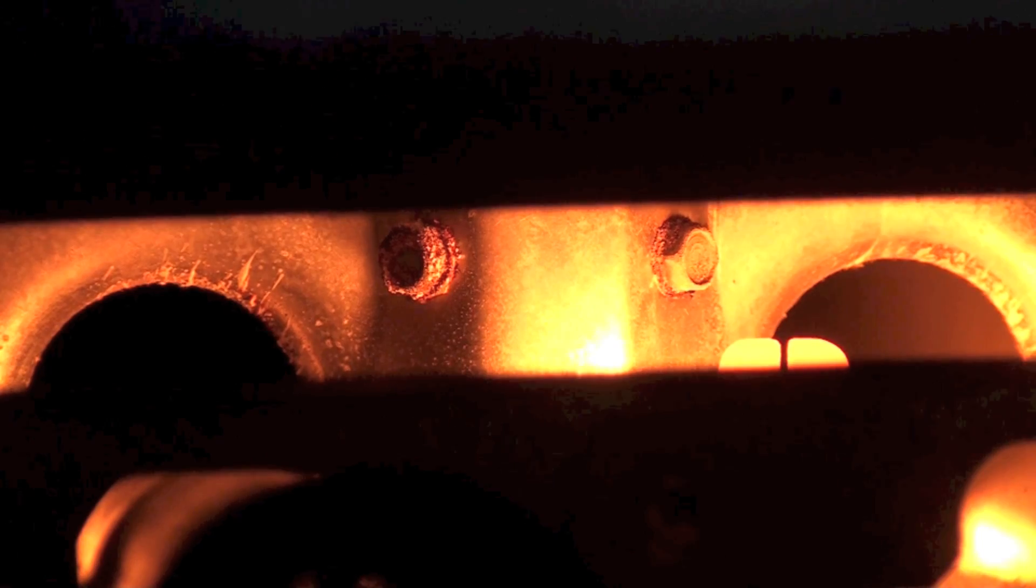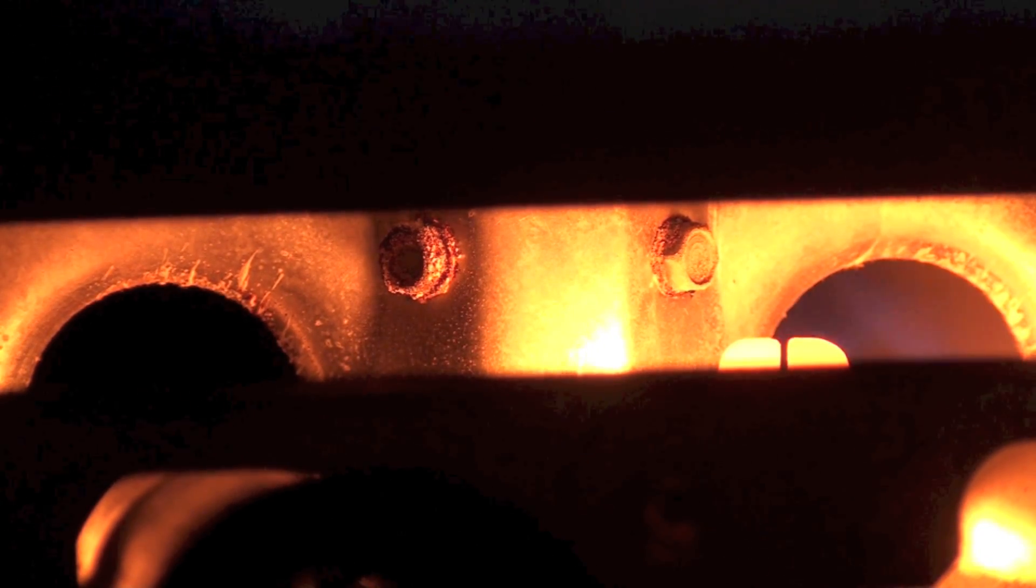So what's going on? Now you see it just safetyed out. Okay, hot surface igniter is on again, there's your burner burning. Didn't travel across to the rest of the burners.